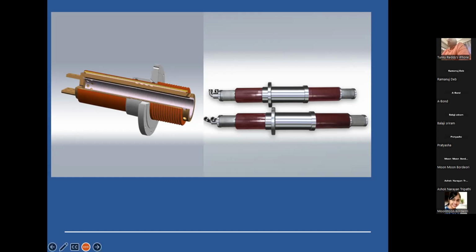So that's why, in this particular application where you have to cool from inside, hydrogen is filled into the conductor, and it has to be absolutely leak-proof. On top of that, we do the insulation so that the insulation capabilities are also taken care of, and the practical application of the hydrogen cooling happens. These are for the big one. Understood. You got the point? Yes, sir, I did. Thank you very much.